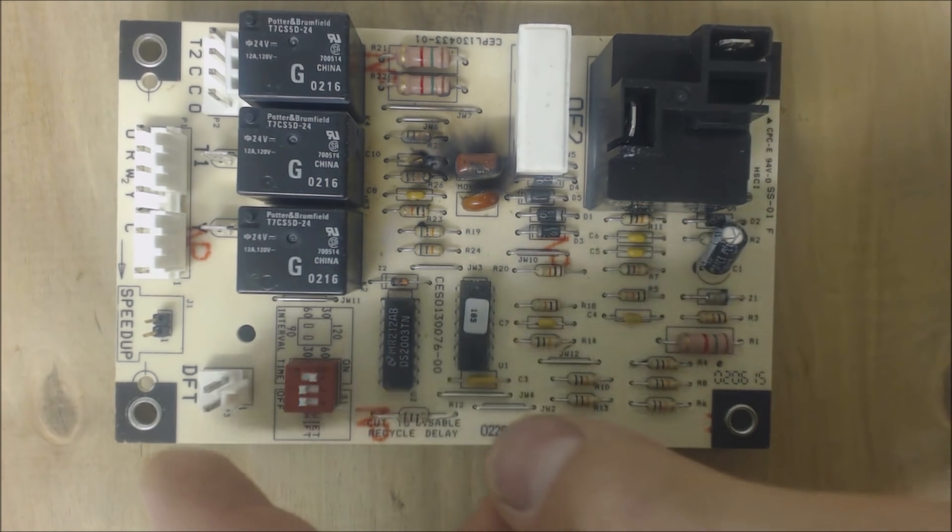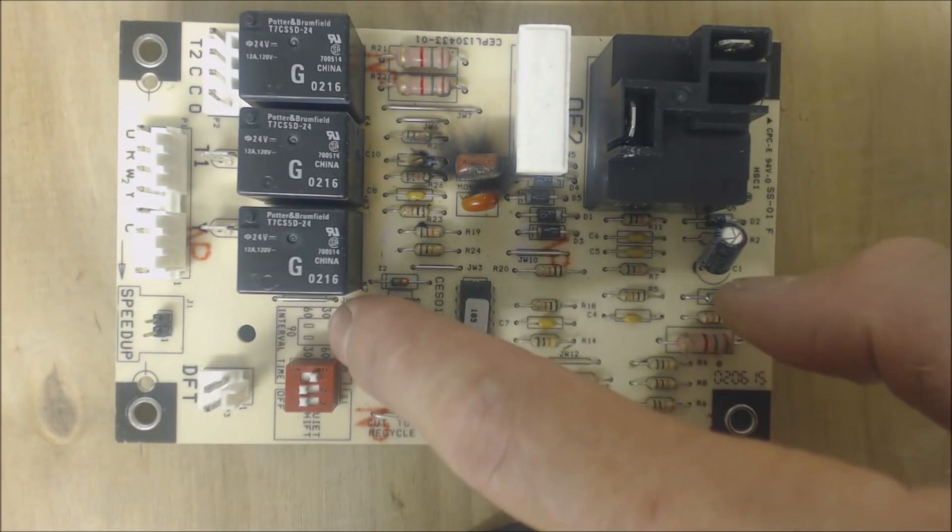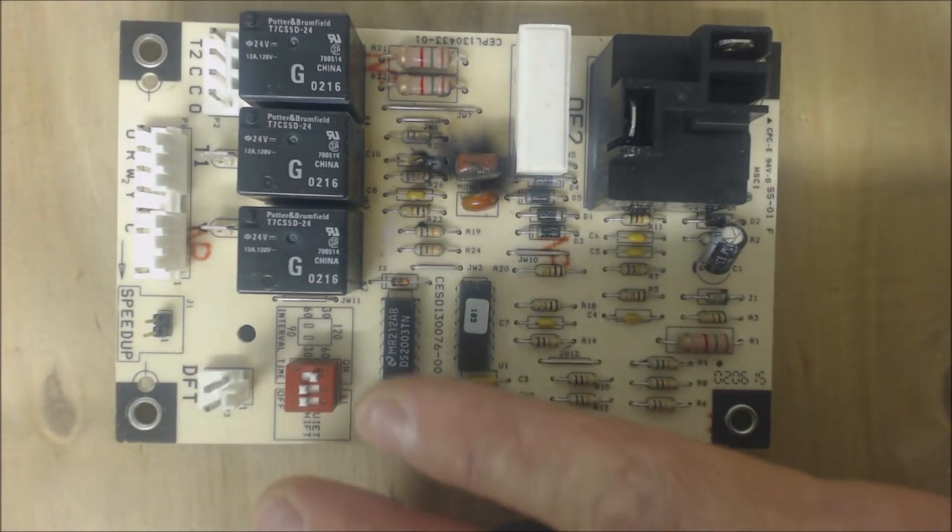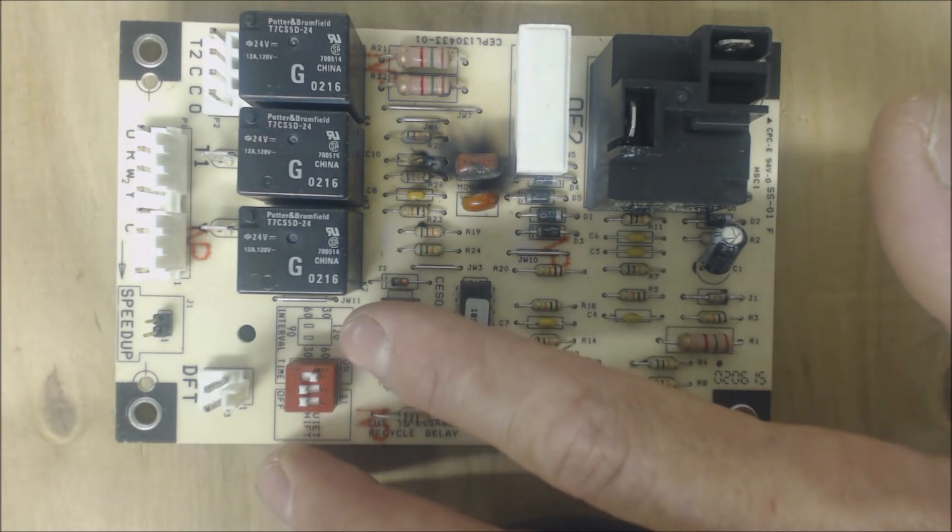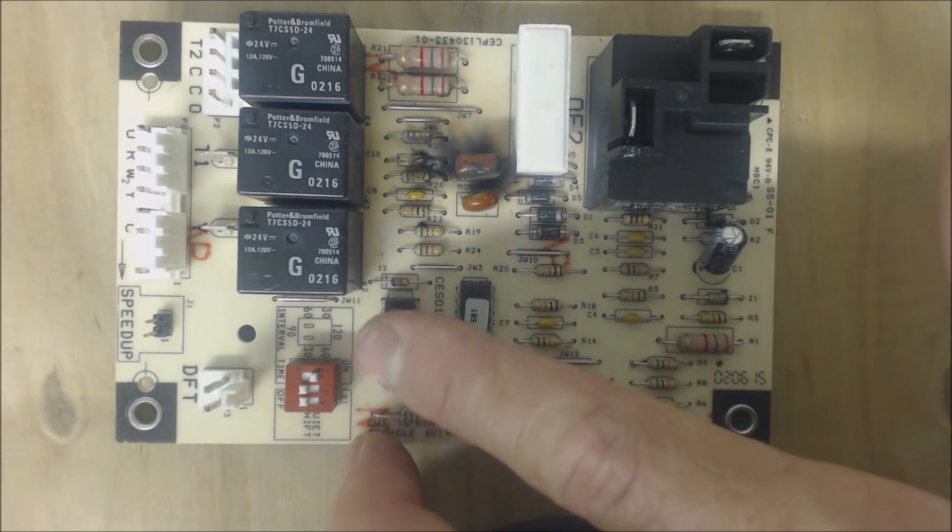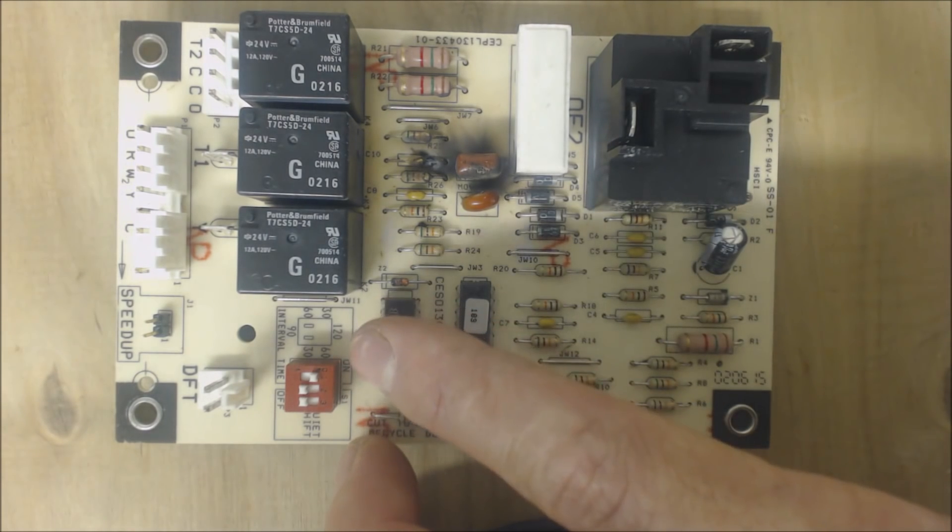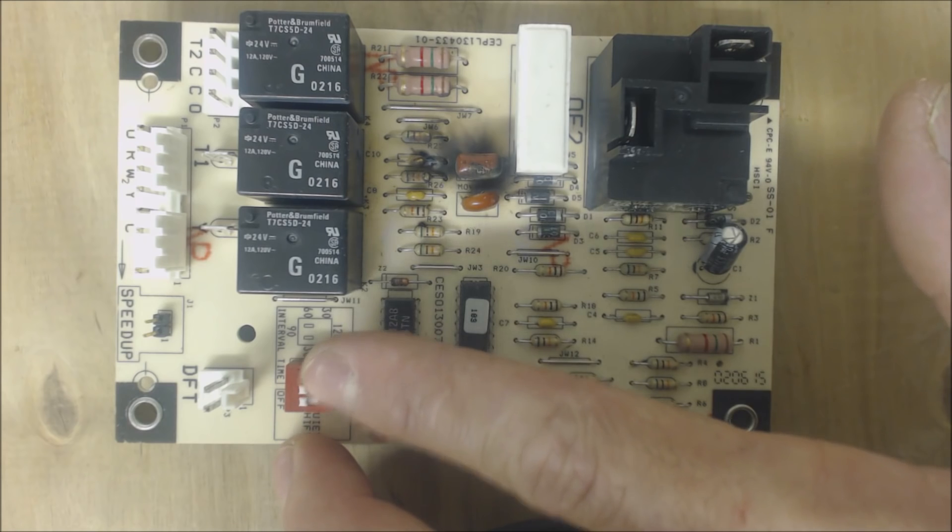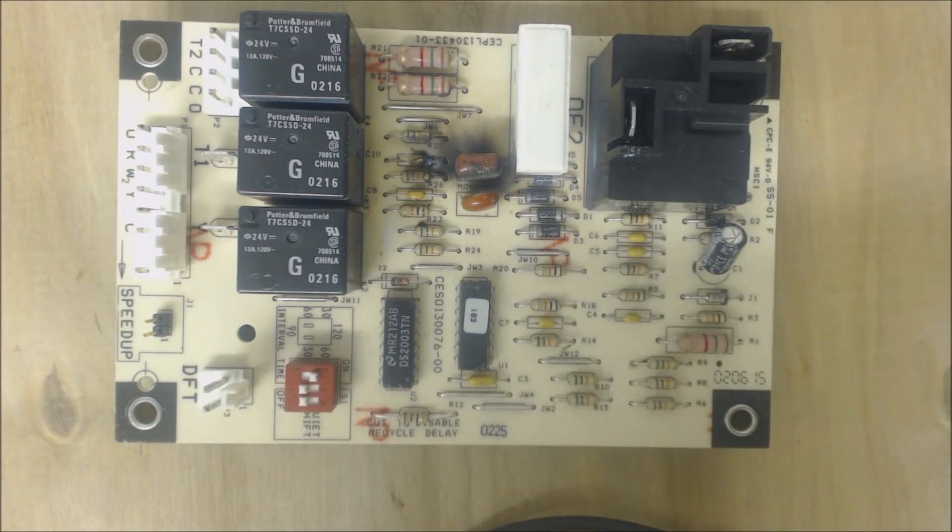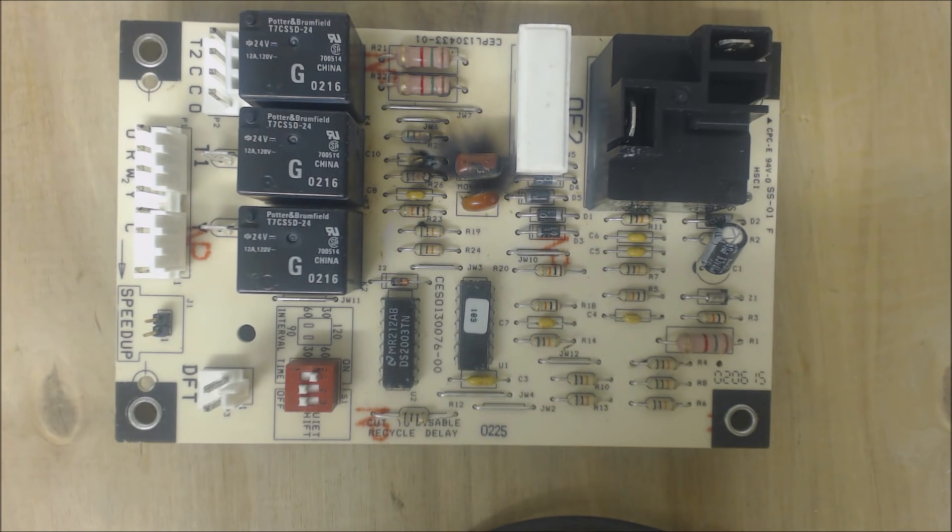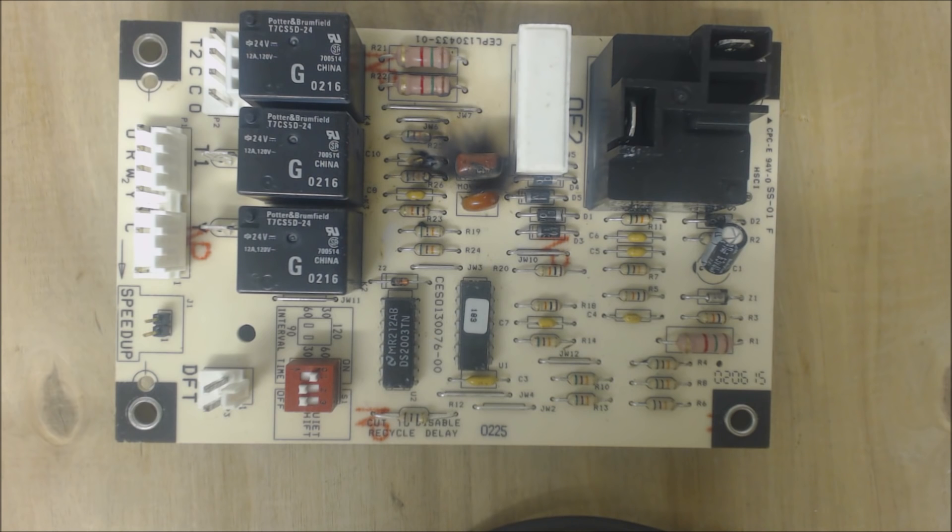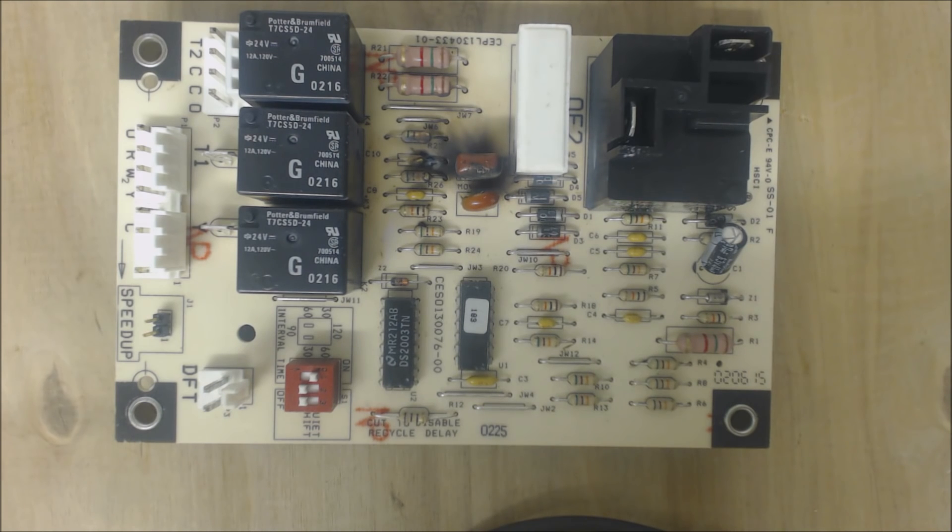Now defrost will actually, if this time requirement, and that's just for any time requirement of the heat pump running, it's going to start counting up the minutes. It doesn't matter what temperature it is. It's going to start counting up the minutes in a cumulative fashion. Once it gets to the upper limit of, say, 90 minutes, if this DFT is closed, it will start defrost. The DFT could be closed even if it's 40 degrees outside. Because you've got to remember that the outdoor fins have to be colder than the outdoor air in order for it to absorb any heat from the outdoor air. So if it's 40 degrees outside, the coils are certainly below freezing, and that will end up closing the DFT terminals. But that's how that works.